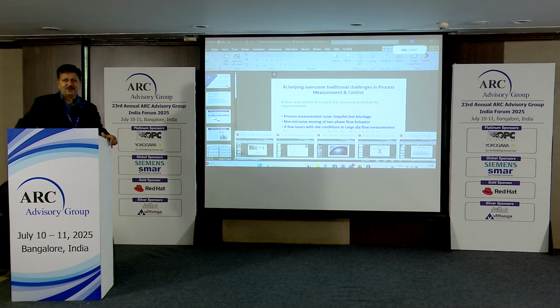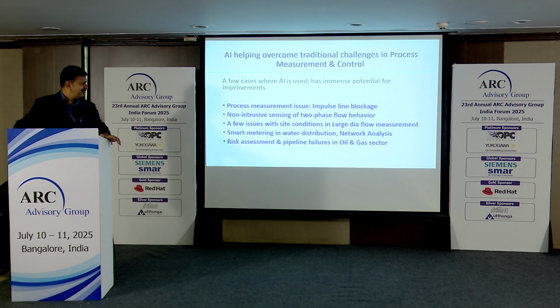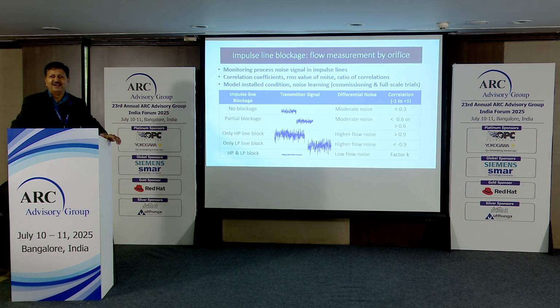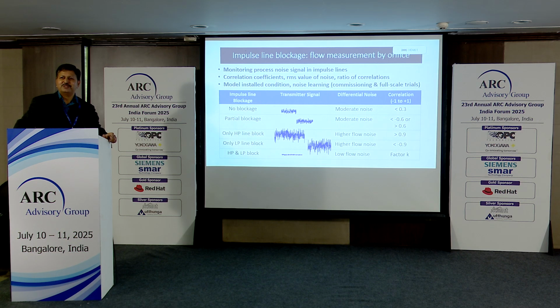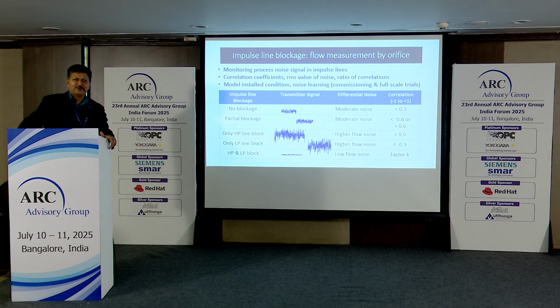Basically, the impulse line study experiments were done with oil as the product flow, and we tried to simulate the blockages by means of certain valves or by freezing the impulse tubes. Based on this, we used high speed data acquisition. We logged the data from the differential pressure transmitter. These are basically the outputs from very common DP transmitters, 4 to 20 milliampere signal.